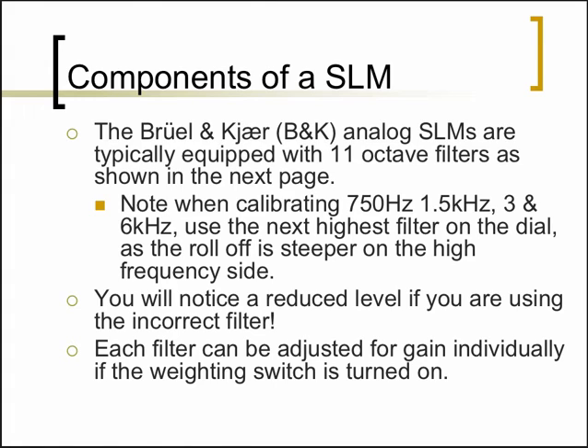So you'll notice that you'll have a reduced level if you're using the incorrect filter, and that becomes especially important when you had those analog sound level meters, where you have to physically change the external filter to the frequency that you're testing in. Nowadays, with the digital sound level meter, it automatically shifts to the appropriate frequency that you're testing in. Okay.